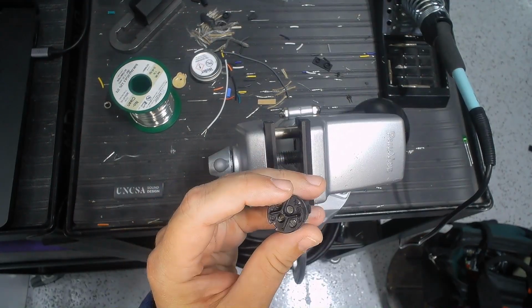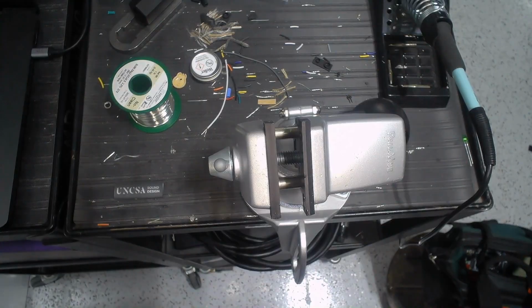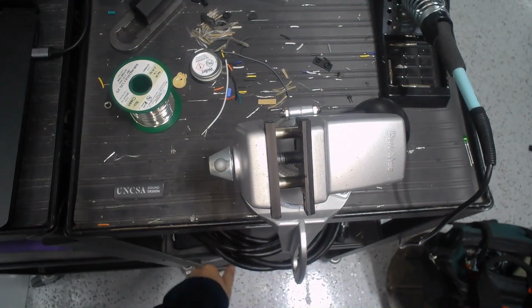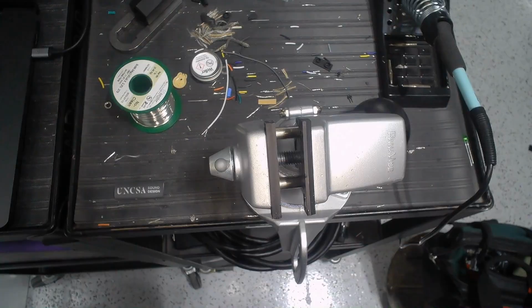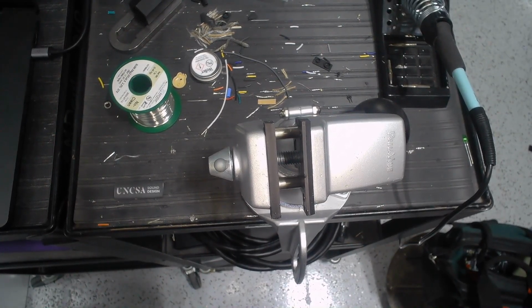And so the wires are a lot thicker. The cable you're going to be working with is 12 gauge, so it's a lot thicker wire, there's a lot more copper in there. Because when you run electrical energy down a wire, it can do a couple things with that energy: it can send it down the wire relatively unimpeded, or it can make heat out of it. Those are the two possibilities. And depending on how thick that wire is and how much energy you're trying to put down it, that will determine how much heat gets made versus how much energy gets to move.